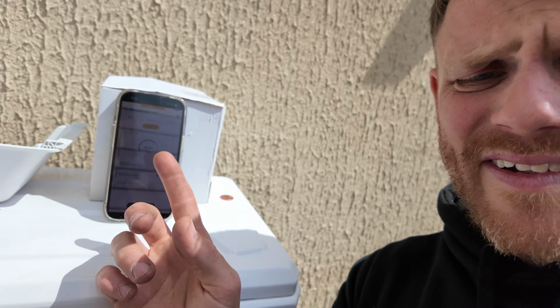The good thing about having that Testo I showed you earlier is it's on your phone, so you're not trying to really gauge it - it's within 0.2 of a decimal place of a bar. If I show you there, it's reading 44.62. On a mechanical gauge you've got to look carefully to know exactly where it is. With this, we already know what it started at and what it's going to end at.